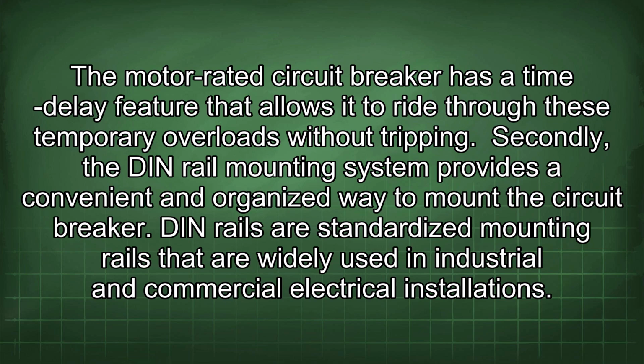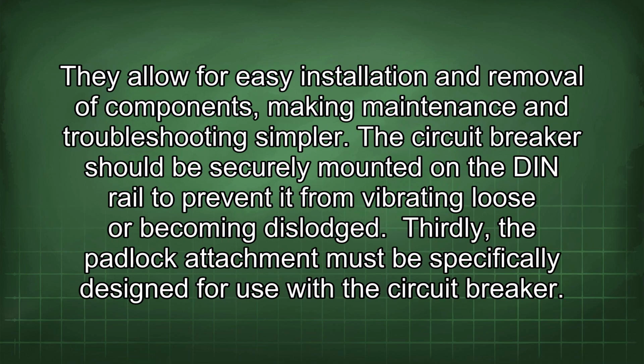Secondly, the DIN rail mounting system provides a convenient and organized way to mount the circuit breaker. DIN rails are standardized mounting rails that are widely used in industrial and commercial electrical installations. They allow for easy installation and removal of components, making maintenance and troubleshooting simpler. The circuit breaker should be securely mounted on the DIN rail to prevent it from vibrating loose or becoming dislodged.